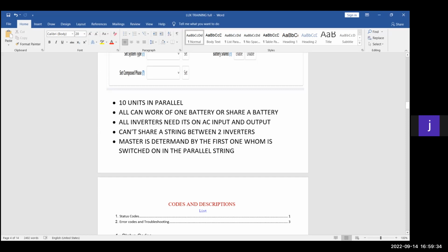And then all the inverters need to have AC input to work. If it's a parallel system, you can't give AC to only one, it will not be happy. Then generator port as well. If it's a parallel system, all the inverters in the system need to have power on the generator port, and install a circuit breaker for the generator port as well, please.